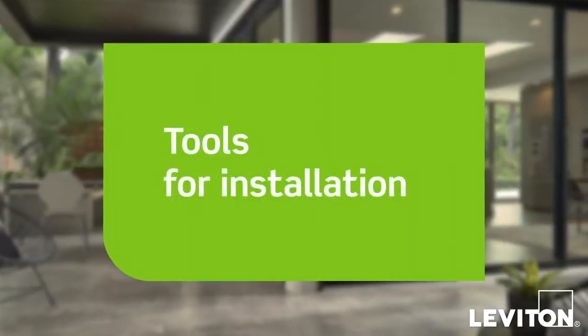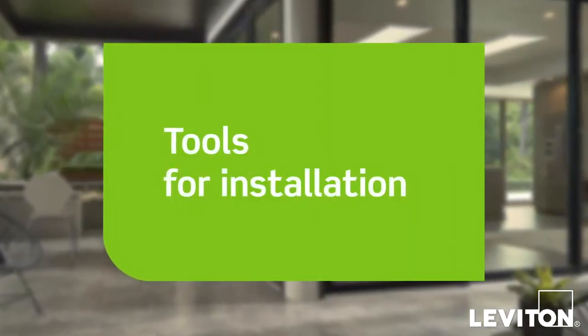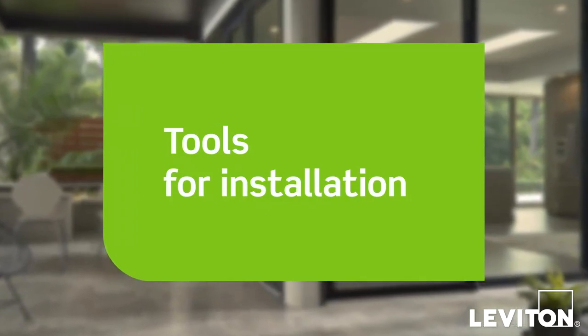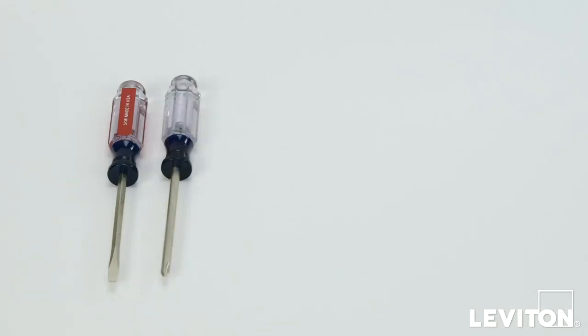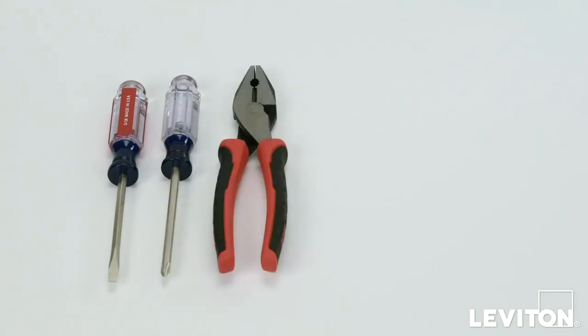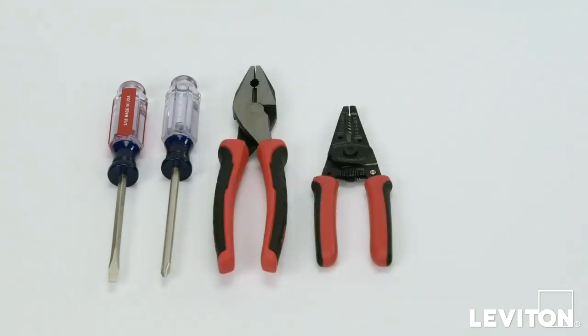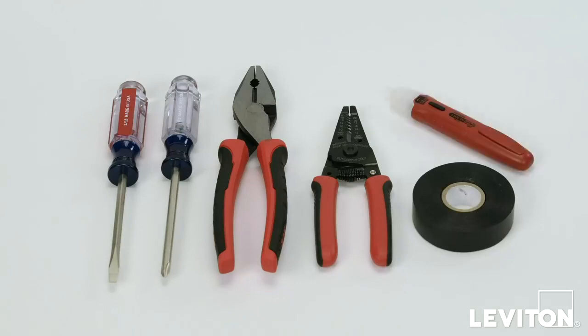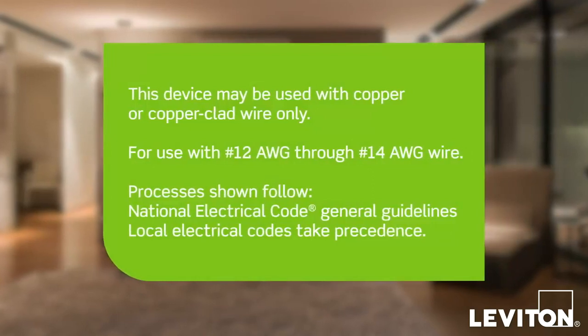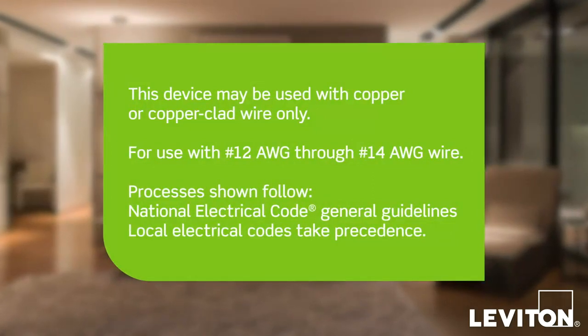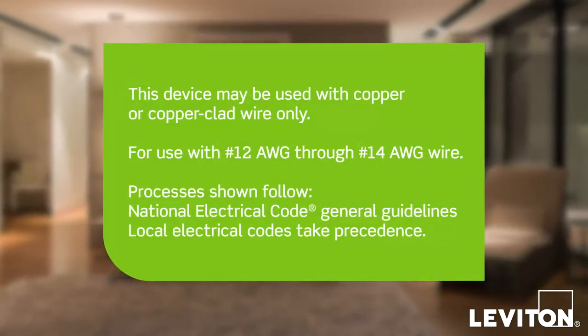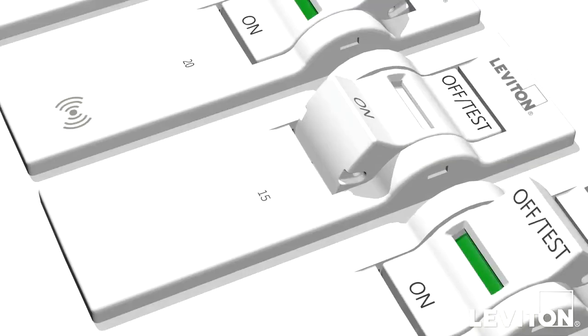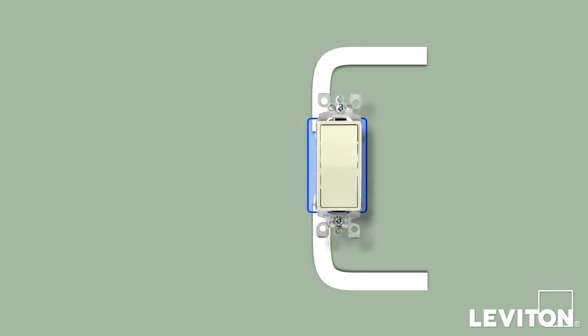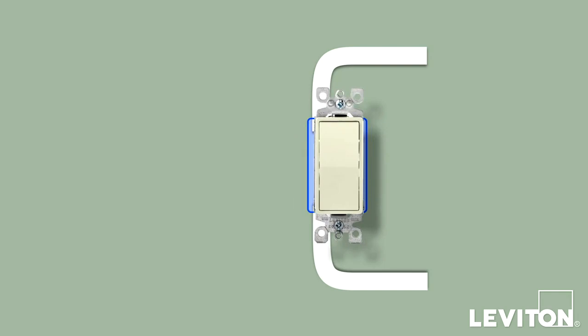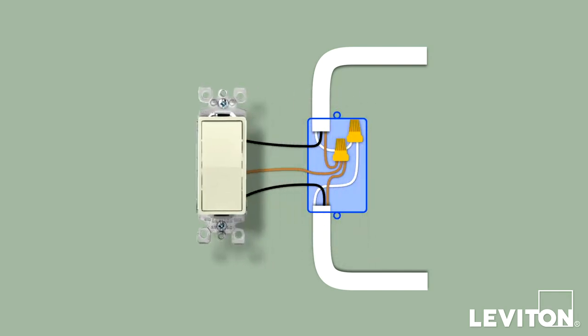When installing and terminating your Decora Smart Wi-Fi 2nd Generation device, have the following tools on hand: a flathead screwdriver, a Phillips head screwdriver, electrician's pliers, a wire stripper, electrical tape, a handheld voltage tester, and properly sized wire connectors. The installation process shown here follows the National Electrical Code General Guidelines. Local codes take precedence. First, turn off the circuit breaker, remove the switch plate, and unscrew the old device from the wall box. Carefully pull the device out until you clearly see the wires.